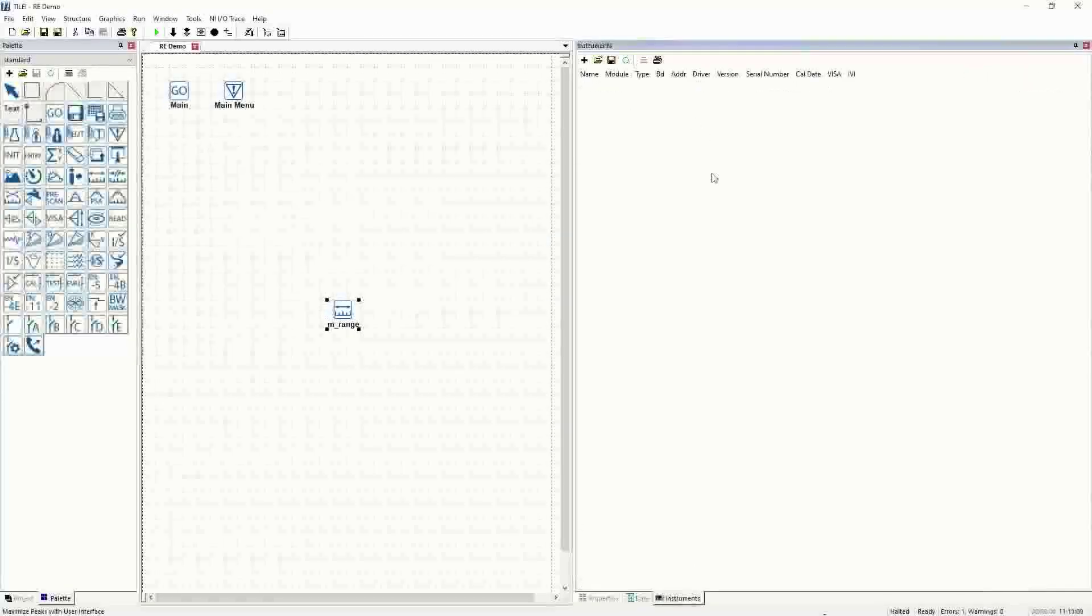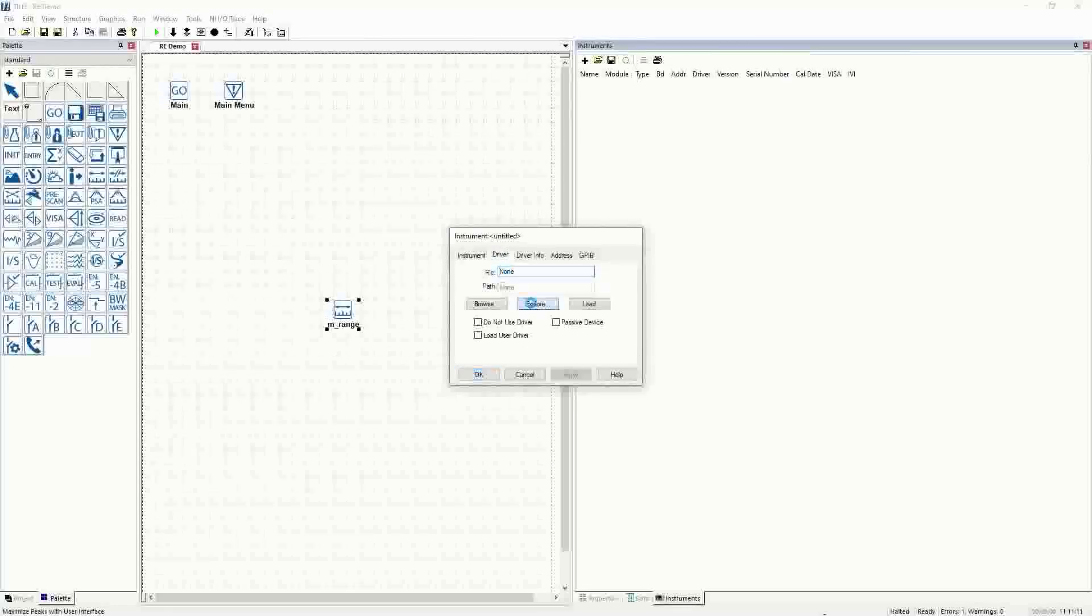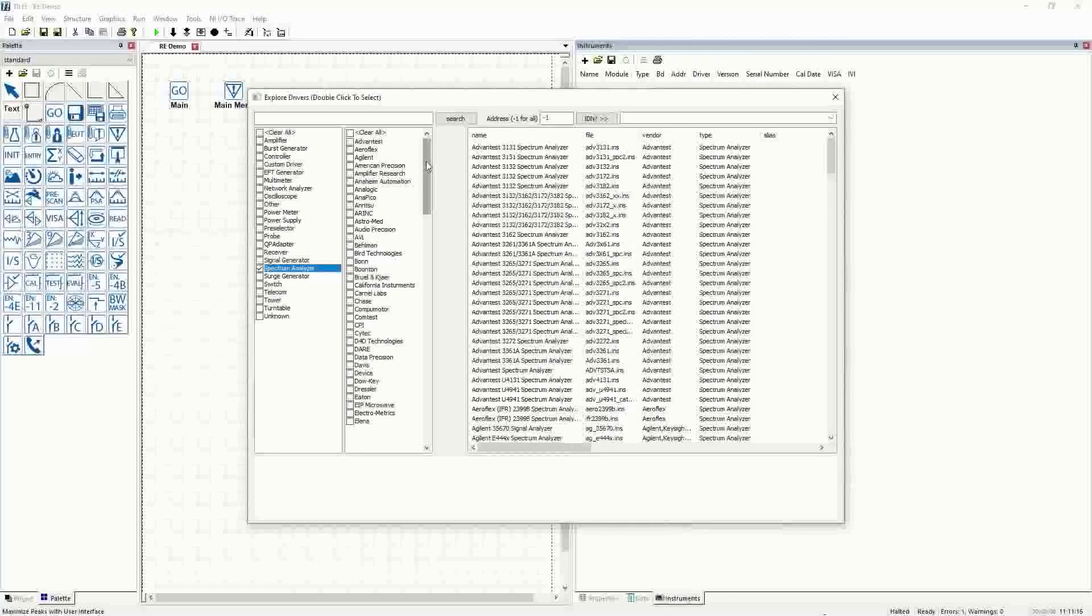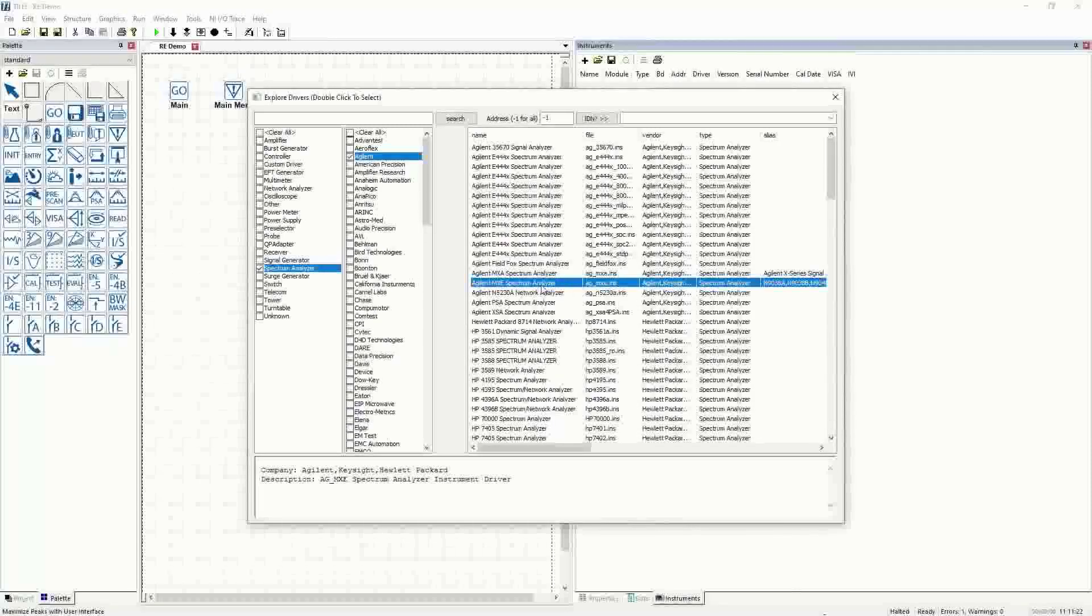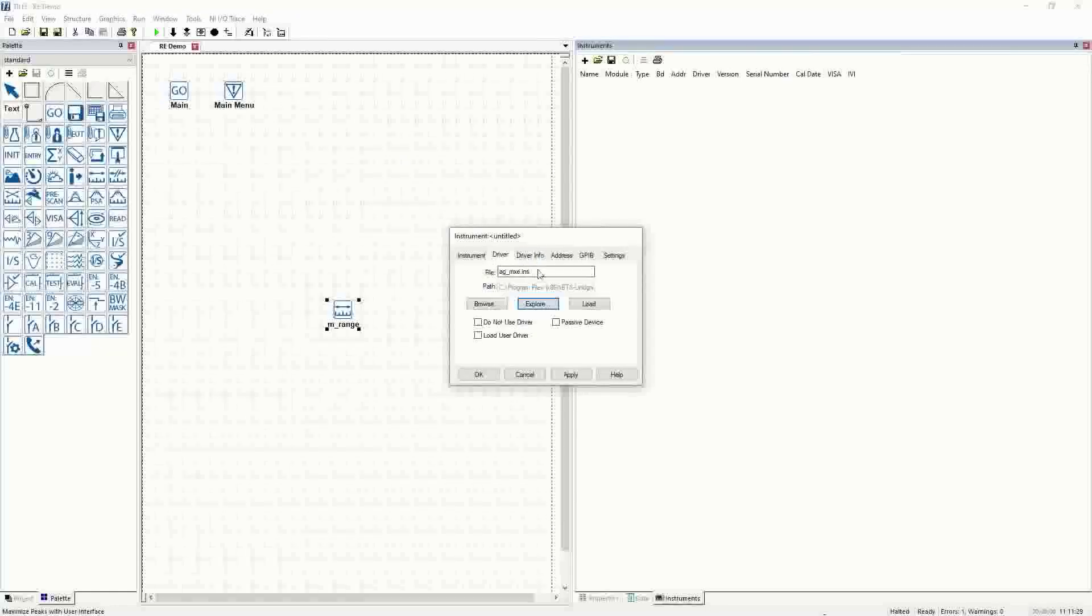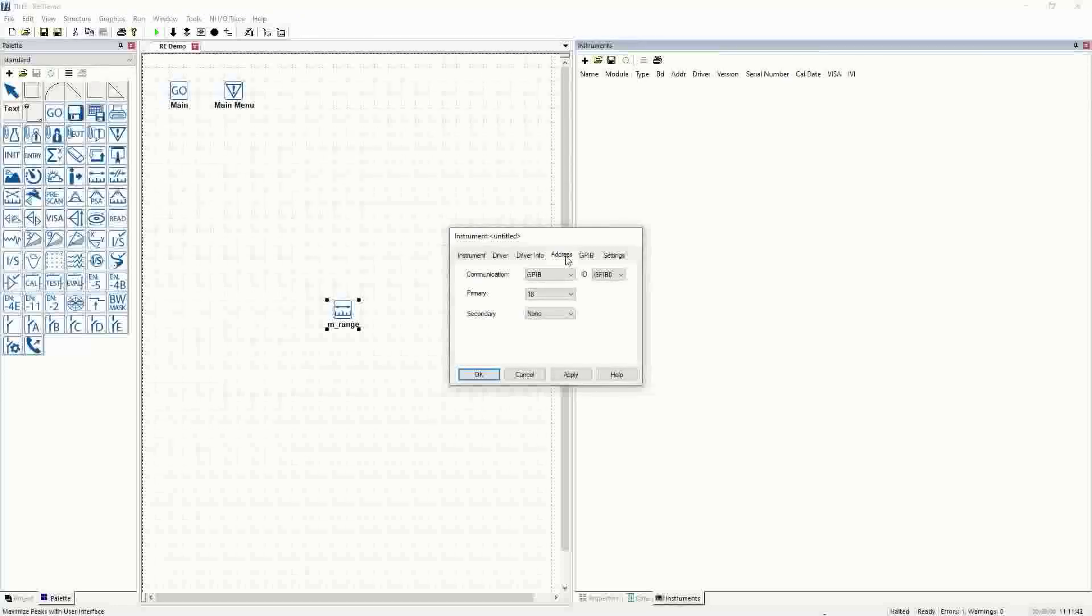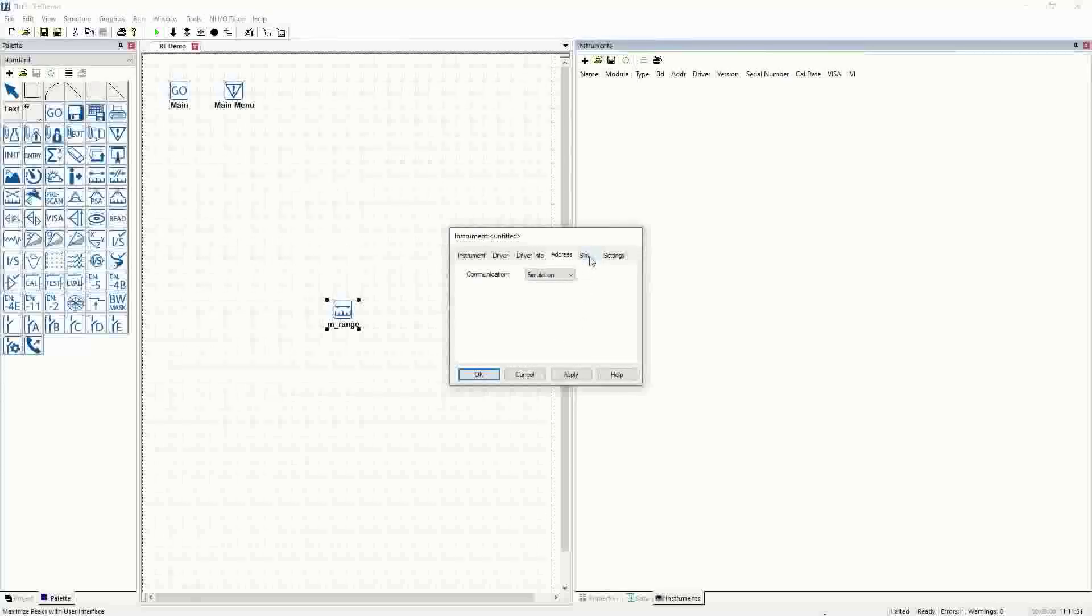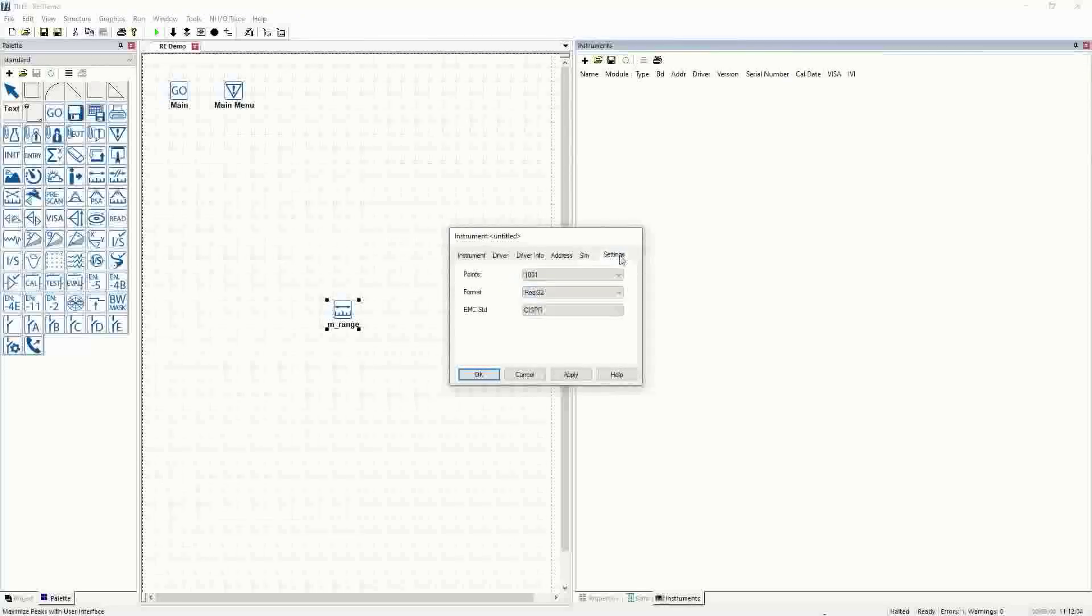Then we'll create an instrument. We'll come here to the instrument panel, click add the plus sign, and we're going to name this specan. We'll go to our driver explorer and select spectrum analyzer, select Agilent. In the list, we have an MXE - that driver works very well with the simulator, so we'll use that driver for the sim. You can see that's been loaded. The driver info tab has some information about the driver and tile version. Then we get to the address tab. We're not actually connected to the box, so we need to simulate the instrument. In the communication block on the address tab, we can select simulation. That changes this panel. Now the sim panel has a type of instrument you're simulating, and it has already selected analyzer, which it should. It places the timeout at 10 seconds - 10,000 milliseconds is 10 seconds.